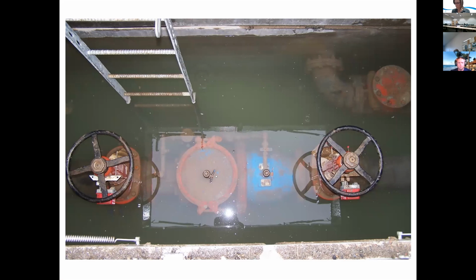In this situation, it would pull the swamp water through the backflow assembly. Rules say that these have to be plugged if they're going to be in a vault, below ground. And RPBAs cannot be in a vault. And if there is a vault, there should be drainage.